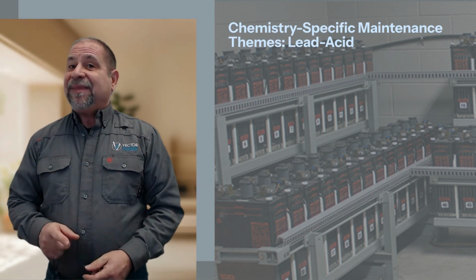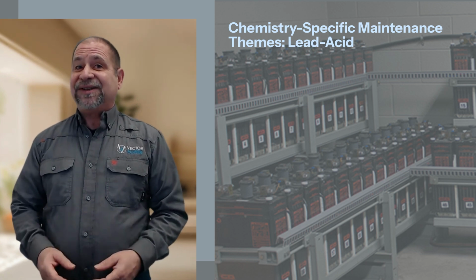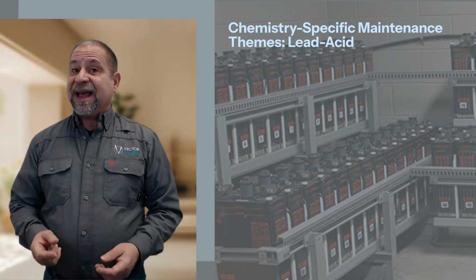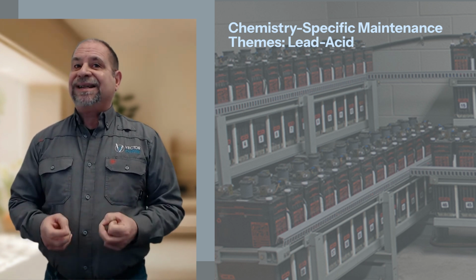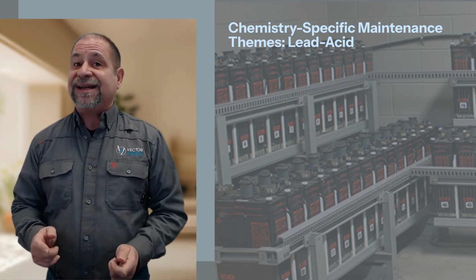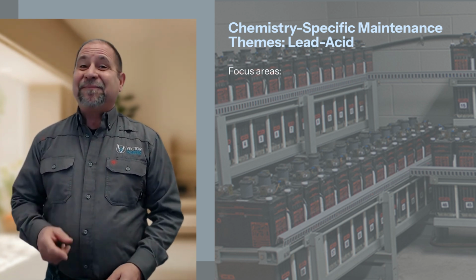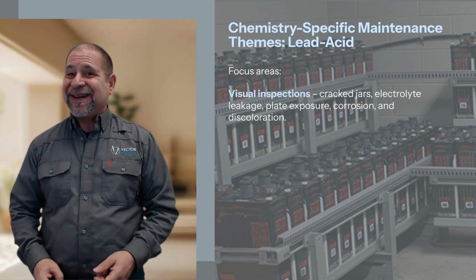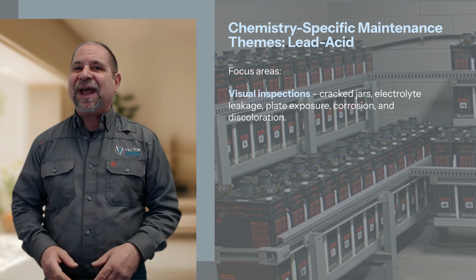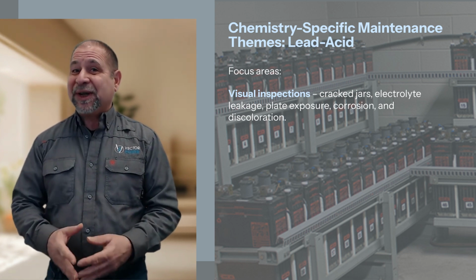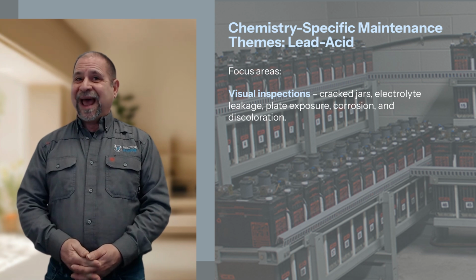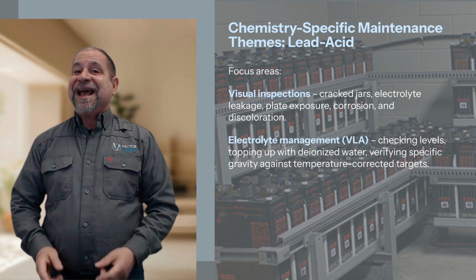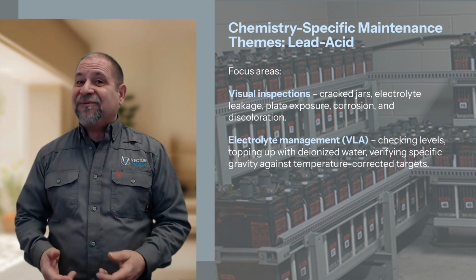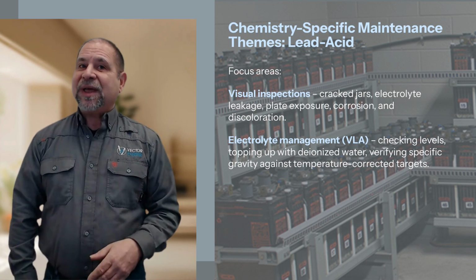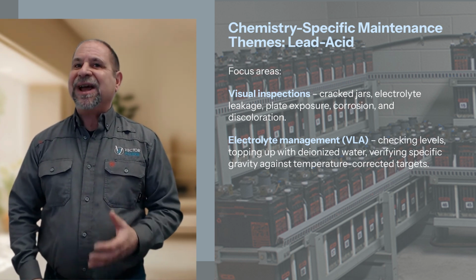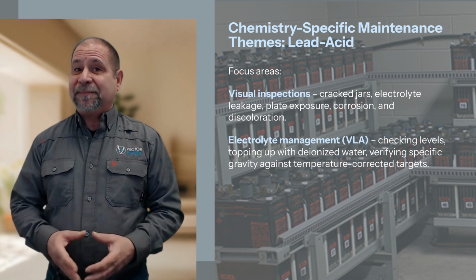Now, let's look at chemistry-specific maintenance themes. We will begin with lead acid batteries, vented lead acid, and valve-regulated lead acid. Focus areas. Visual inspections. Check for cracked jars, electrolyte leakage, plate exposure, corrosion, and discoloration. Electrolyte management for vented lead acid types. Checking levels, topping up with deionized water, verifying specific gravity against temperature-corrected targets.